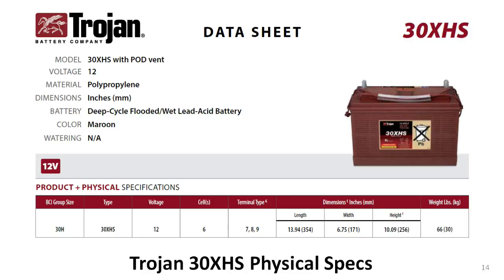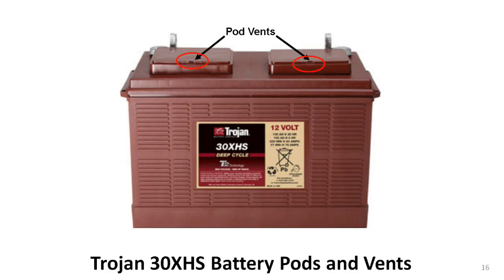Here's the top section of the front page. Starting at the top left, just under the Trojan logo, there is the model number 30XHS and the words 'pod vent.' Trojan has chosen to call the cell covers pods, and each cover has a small hole at the top center of the front edge — those are the pod vents. They allow gases to escape from inside the battery and are your tip-off that the 30XHS is not a sealed battery, so if you turn it over, the electrolyte will spill out.